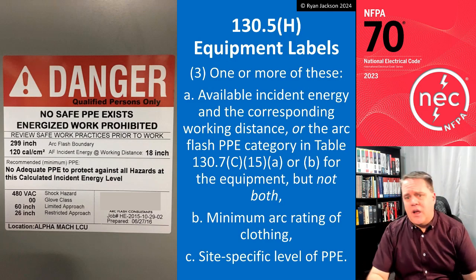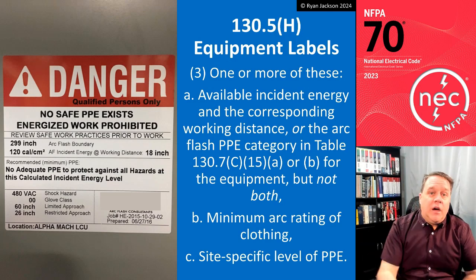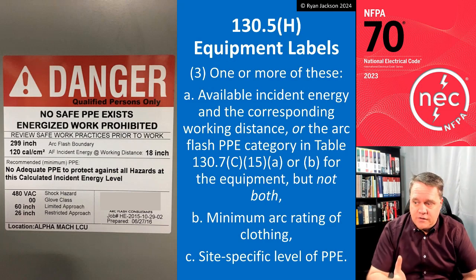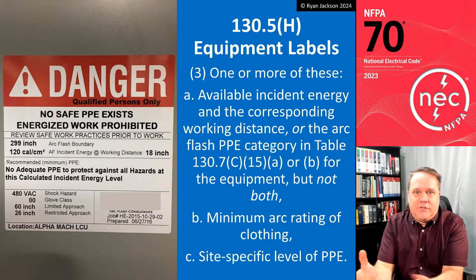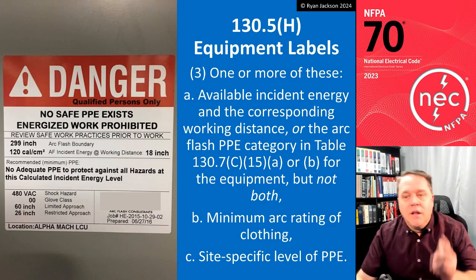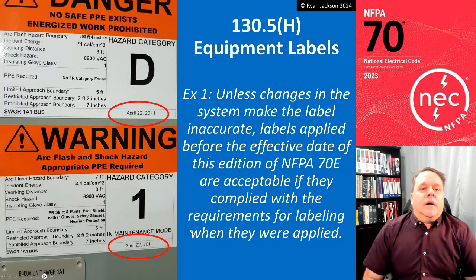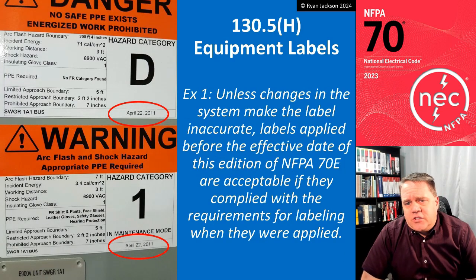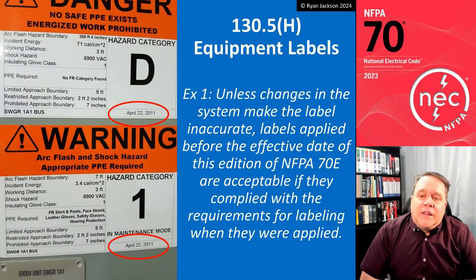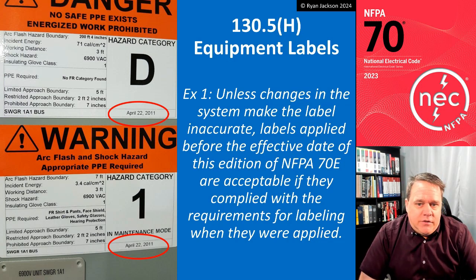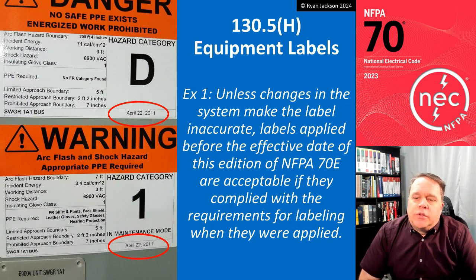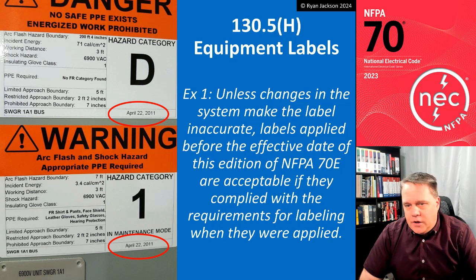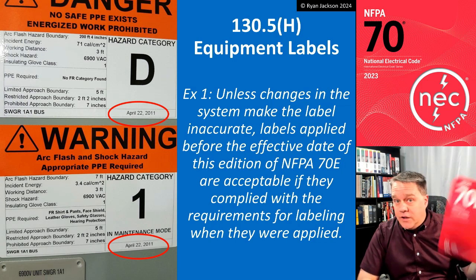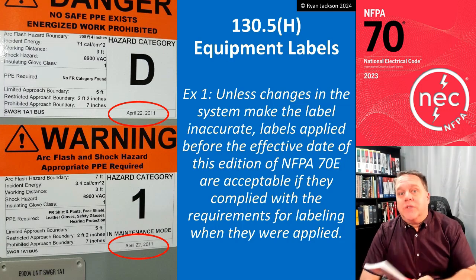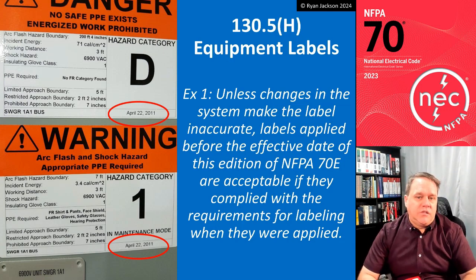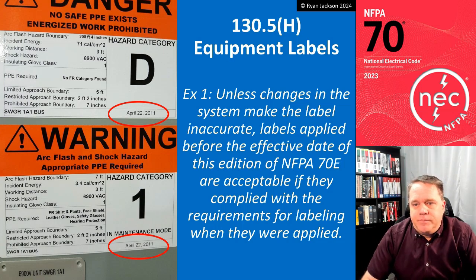So don't try to do a site-specific thing. Just look, tell me how to dress, all right? And let's not make it archaic, and let's not make it esoteric, so I don't have to have some sort of manual to tell me what it means, okay? Just tell me how to dress. We've got an exception that says, unless changes in the system make the label inaccurate, labels applied before the effective date of this edition of 70E are acceptable if they complied with the requirements for labeling when they were applied. Okay. Do I need to go through every 3 years when they make a standard and put new labels on? No, we don't, unless we've changed the system to make the labels inaccurate.